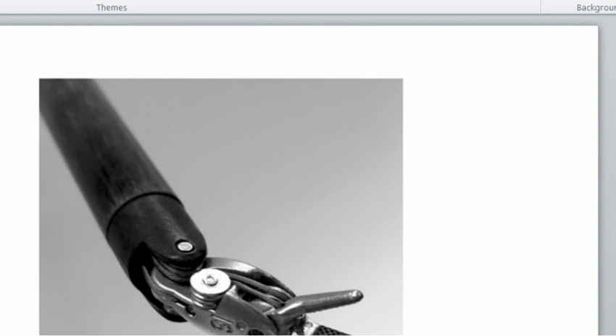Since it was developed, this instrument has been successfully used in many experiments to investigate characteristics of soft tissue in both in vitro and in vivo conditions. However, because the sensing elements are located far away from the tissue interaction point, minimizing backlash and friction of all joints is really important for preventing sources of measurement inaccuracy. So to get rid of possible measurement errors, a robotic force feedback instrument was developed at the Technical University of Munich. It has strain gauges located at the instrument shaft close to the gripper.